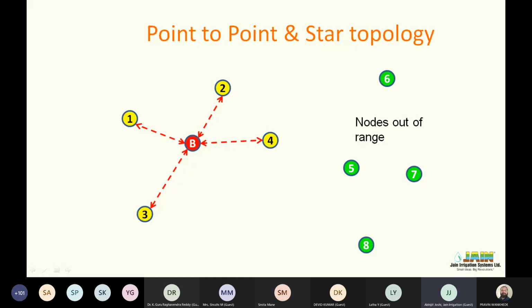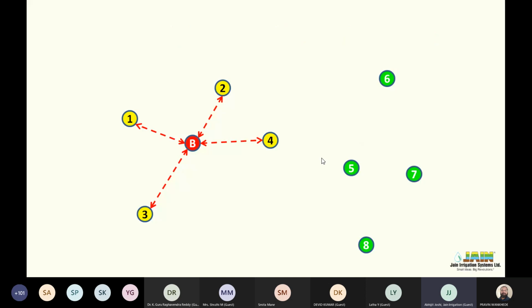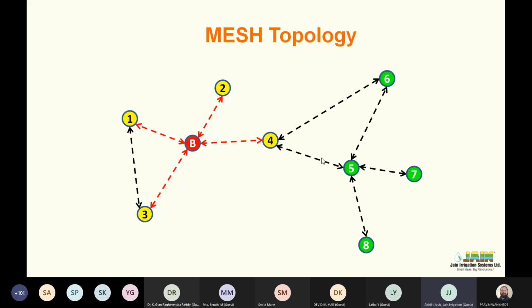So mesh topology is a bit different from star topology. Star topology is point-to-point communication, whereas in mesh topology, each and every RTU tries to form a mesh, and every RTU will repeat the signals, and the base station or gateway will find out the shortest possible route. If any RTU is not working or falls down or something happens, it will still try to find another best possible route for communication.